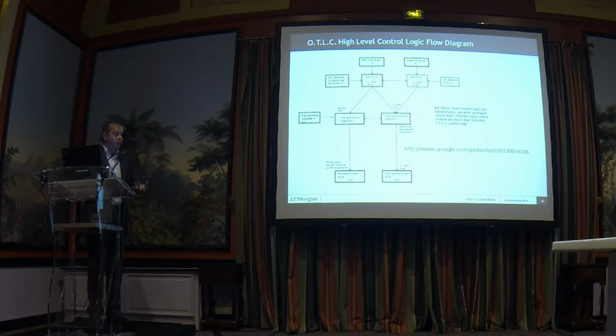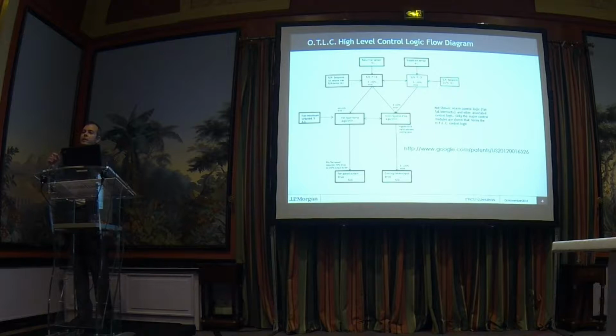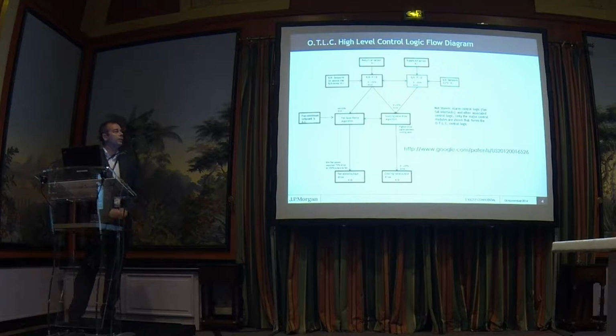So after working out this, supply air looks like the way forward, because we were seeing a lot of air conditioners in a circle, all working together apparently in return air control. And we've got variable speed fan drives in these machines. So what would happen is that the one machine would be close to a hot server, and the sensor in this machine would then detect, well, I'm running really high here, I've got to ramp right up. So all of a sudden you get an air conditioner doing 100% load, full fan speed, full valve opening, supplying 15 or 14 degree supply.